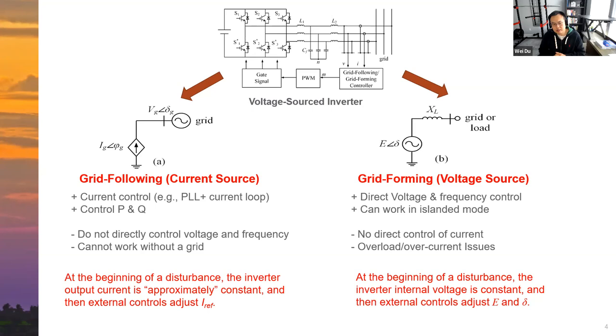To summarize these two controls: for grid following inverters, at the beginning of a disturbance, the inverter output current is approximately constant, and then some external controls adjust the reference signal of this current. For grid forming inverters, at the beginning of the disturbance, the inverter internal voltage is held approximately constant.